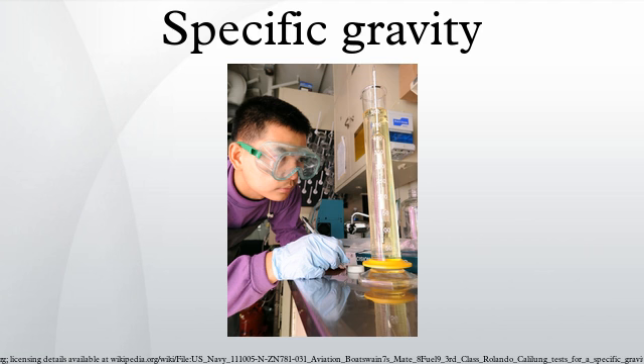Note that the result does not depend on the calibration of the balance. The only requirement on it is that it read linearly with force. Nor does it depend on the actual volume of the pycnometer. Further manipulation and finally substitution of the true specific gravity... The subscript V is used because this is often referred to as the specific gravity in vacuo. It gives the relationship between apparent and true specific gravity.